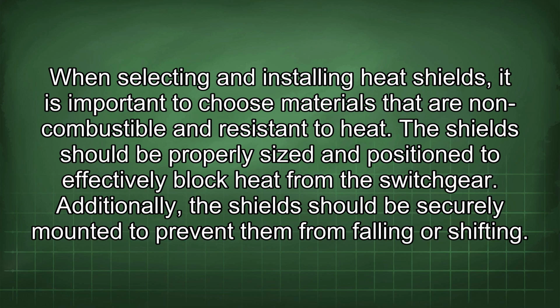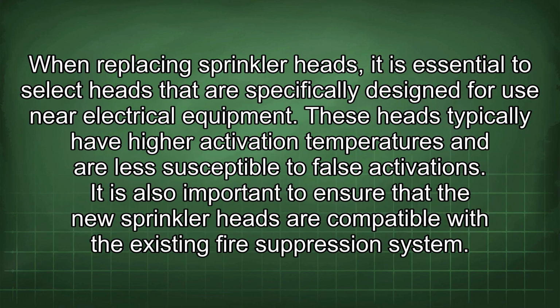When selecting and installing heat shields, it is important to choose materials that are non-combustible and resistant to heat. The shields should be properly sized and positioned to effectively block heat from the switchgear. Additionally, the shields should be securely mounted to prevent them from falling or shifting. When replacing sprinkler heads, it is essential to select heads that are specifically designed for use near electrical equipment. These heads typically have higher activation temperatures and are less susceptible to false activations. It is also important to ensure that the new sprinkler heads are compatible with the existing fire suppression system.